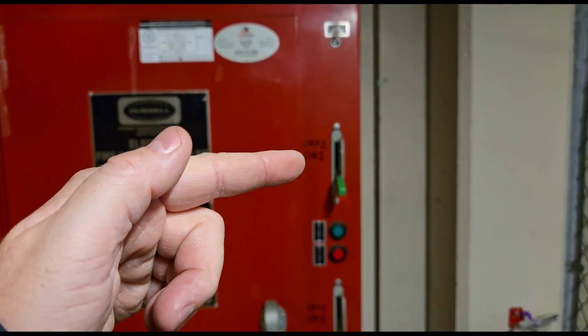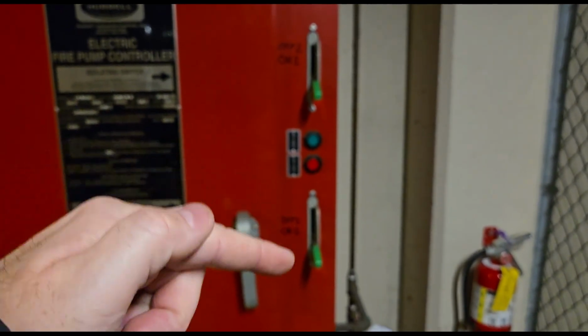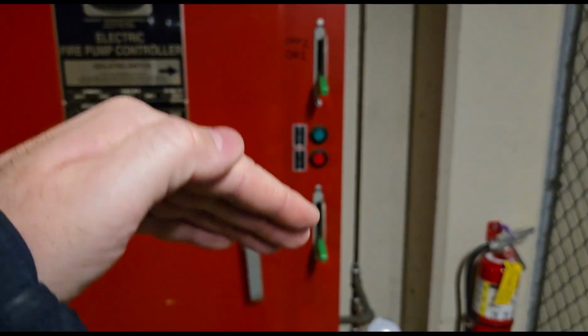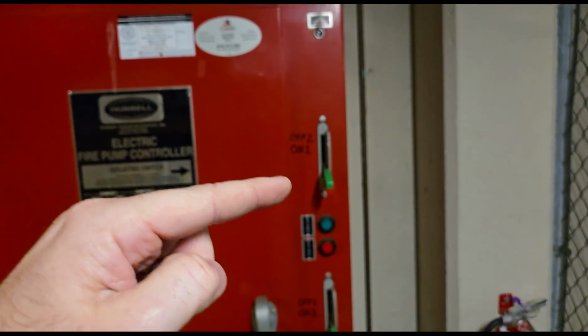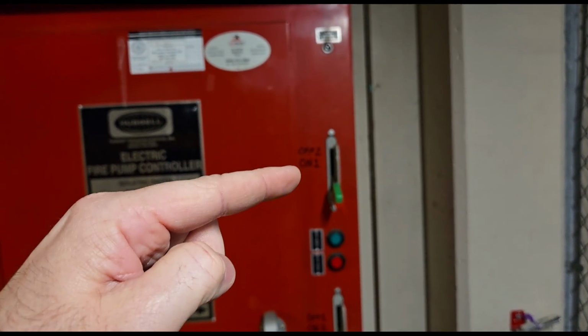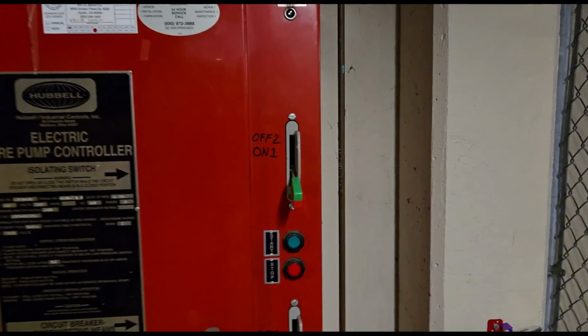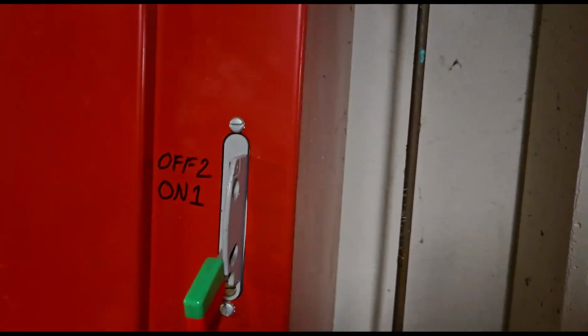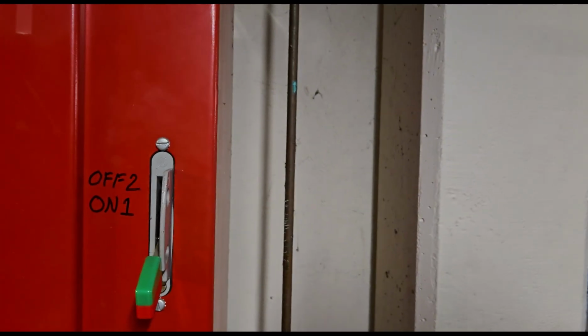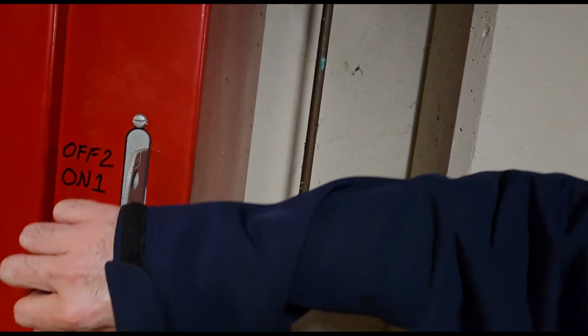And then we operate the switch. Since it's already open, in the down position, I can now turn on the isolating switch. Again, I'm going to come over, stand to the side of the pump to protect myself from any arc flash, and turn on the isolating switch first.